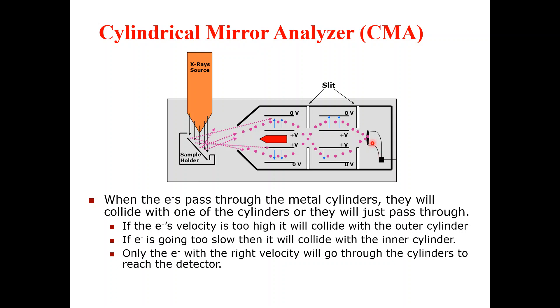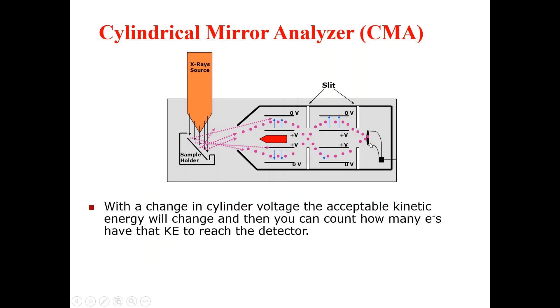Only those electrons with the right velocity will be analyzed for the composition of the particular sample we are interested in analyzing with XPS. With the change in the cylinder voltage, the acceptable kinetic energy will change, and you can count how many electrons have the kinetic energy to reach the detector — which depends on the change in voltage of the cylinder.